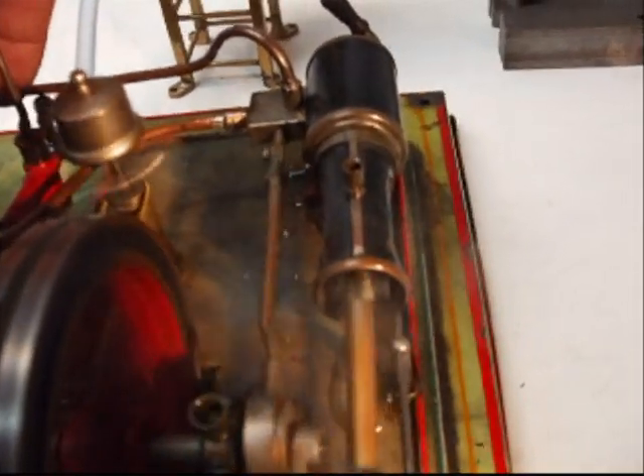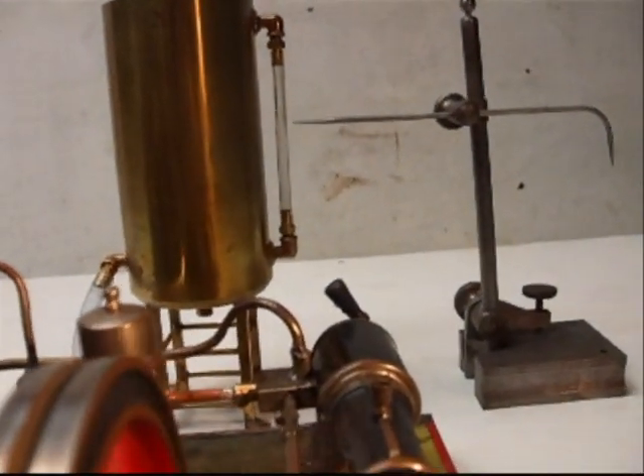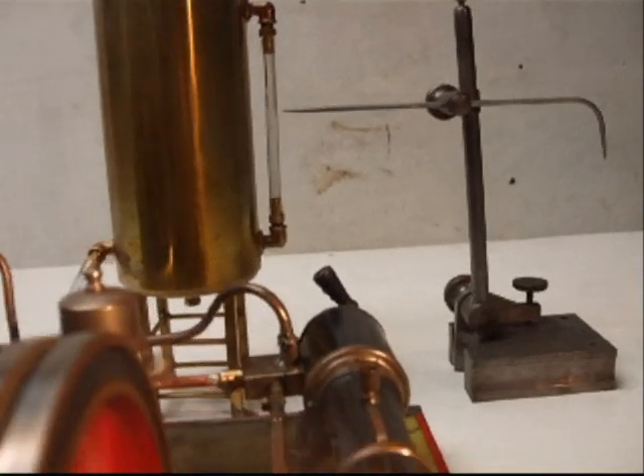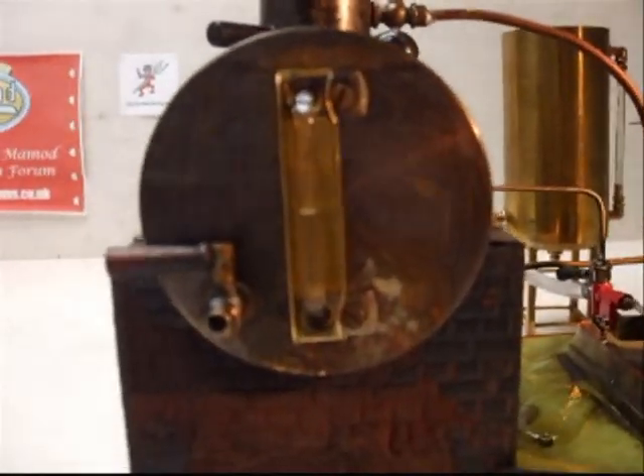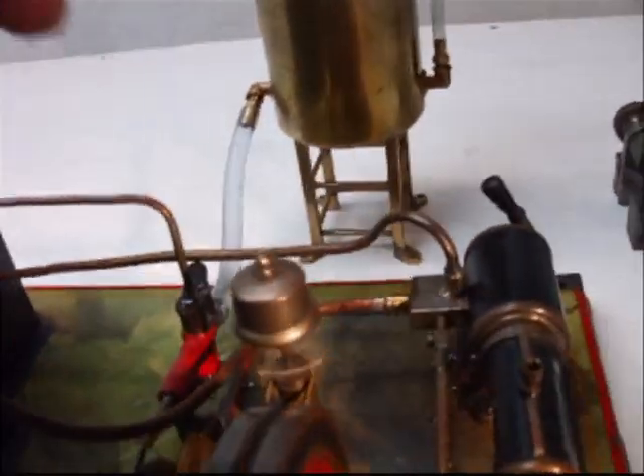There's nothing coming out of there. Just turn on the pump — here comes the water. The pump's leaking a bit. Takes it down to half a bar. The water level's gone up in the header tank. Water level normal though, and it's a big leak.